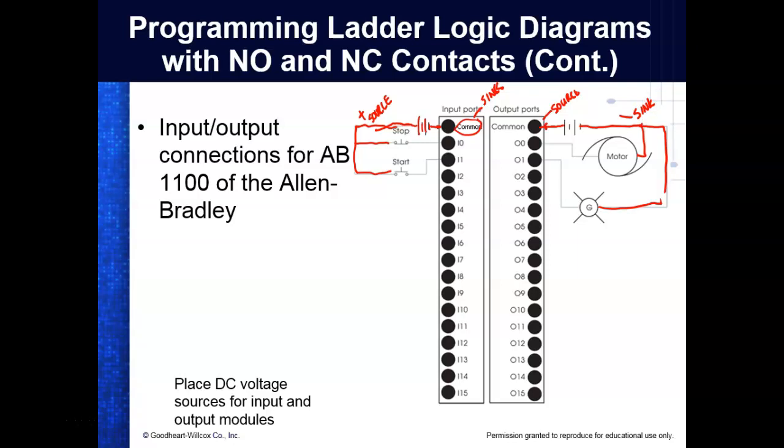So this is pretty important. This guy here has AC outputs. So here I would use the symbol for an AC, and if you've got one of the 1000s, this is the way you'll wire your connection. So we're using sinking inputs, so sourcing devices, and then over here it doesn't make any difference, right? You understand that? So remember, this common right here is 120 volts, guys, on the 1000s. So don't open the little door down here at the bottom. Are we okay? Any questions?